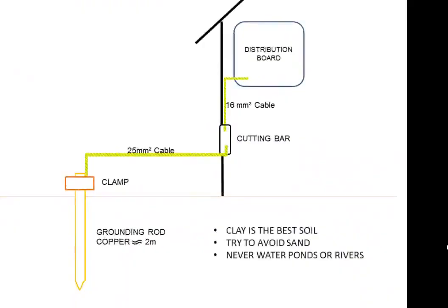Let us see how to install a grounding system. A grounding rod is buried in the soil. The electrical resistance of the soil is very important. It should be as low as possible to make easier the current flow into the ground. The most suitable grounds are clay. We should try to avoid sand and never use water ponds or rivers. Sometimes there is a small layer of sand which can be easily avoided by digging.